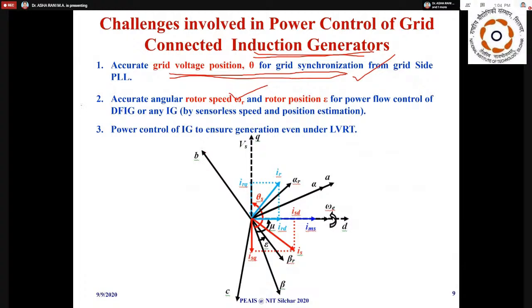So with the normal algorithms, you cannot directly calculate the speed. Especially under unbalanced or distorted grid conditions, special measures have to be taken. And we have to ensure that power control is possible even with low voltage ride through. These are the important things we have to take care of.